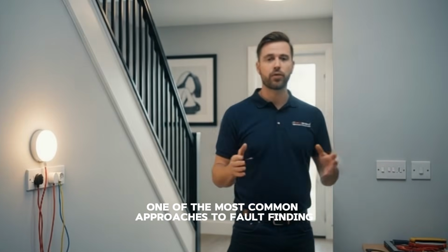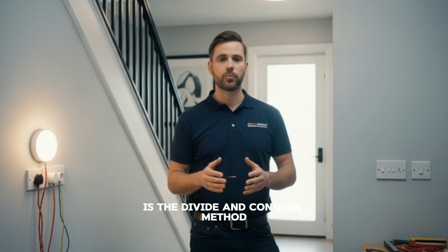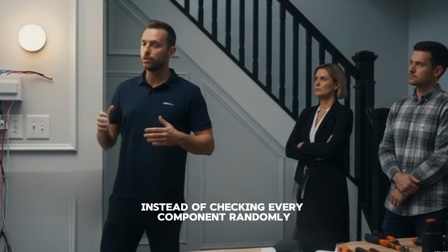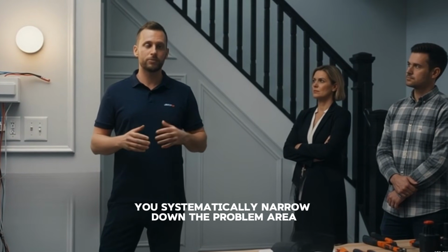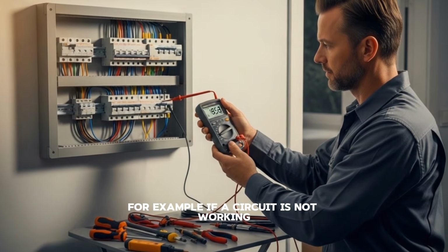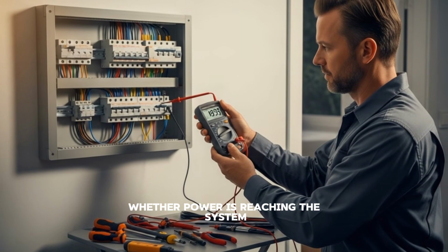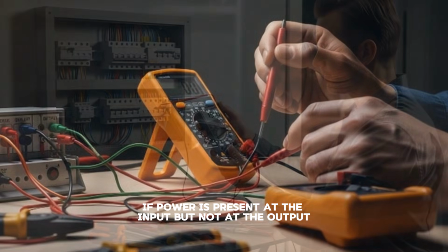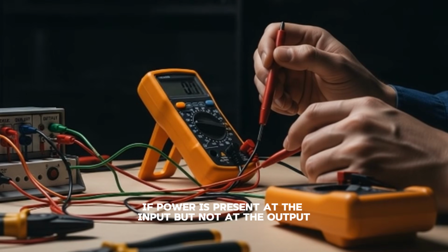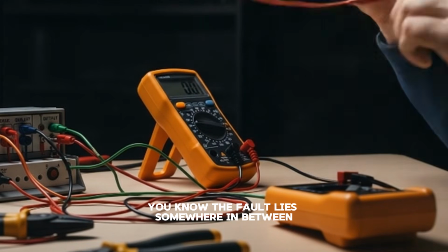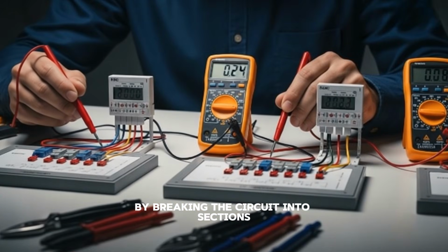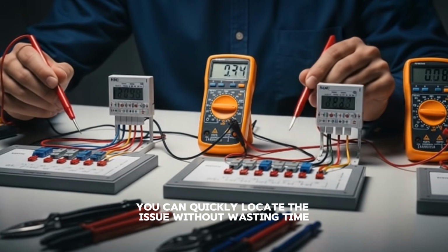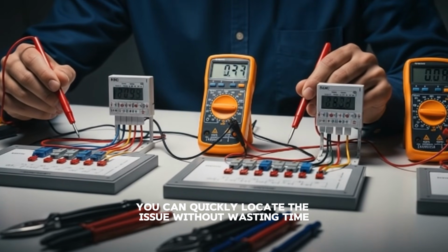One of the most common approaches to fault finding is the divide and conquer method. Instead of checking every component randomly, you systematically narrow down the problem area. For example, if a circuit is not working, you might first check whether power is reaching the system. If power is present at the input but not at the output, you know the fault lies somewhere in between. By breaking the circuit into sections and testing each part, you can quickly locate the issue without wasting time.